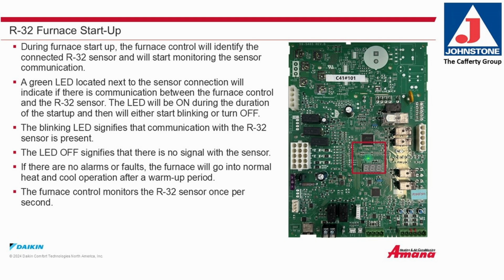R32 furnace startup. During furnace startup, the furnace control will identify the connected R32 sensor and will start monitoring the sensor communication. A green LED located next to the sensor connection will indicate if there is communication between the furnace control and the R32 sensor. The LED will be on during the duration of the startup and then will either start blinking or turn off.